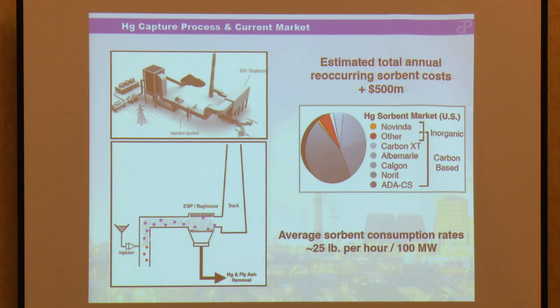So how do people currently control mercury? It's an interesting topic because you don't want to reorganize the whole plant to control one single element. The most convenient way has been injecting a really fine sorbent. The idea is capturing that high mass transfer between small particles and flue gas, with relatively short residence times, so you have to balance those two variables and use existing devices in place to facilitate this removal. Again, we're technically not capturing mercury, we're just moving it from one phase to another, from the gaseous phase into the solid phase.